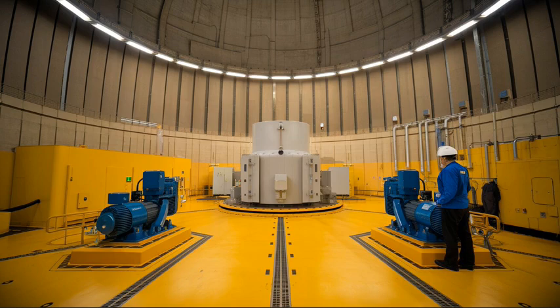Environmental conditions. The motors should be designed to operate in harsh environments with high radiation, temperature fluctuations, and humidity. That is, special insulation and protection measures should be implemented to prevent degradation over time. Use motors with appropriate enclosure types, for example, IP55, IP65 to protect against dust, moisture, and other contaminants. Monitoring. The motors should include provisions for vibration sensors to monitor performance and detect early signs of mechanical issues like misalignment or bearing wear.